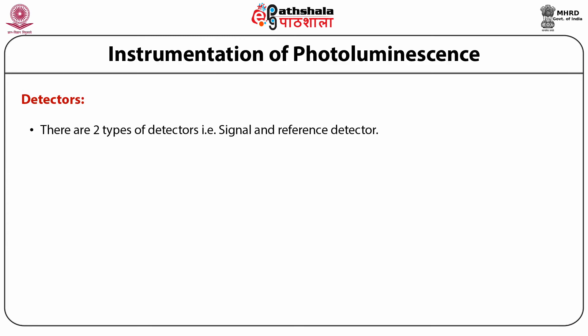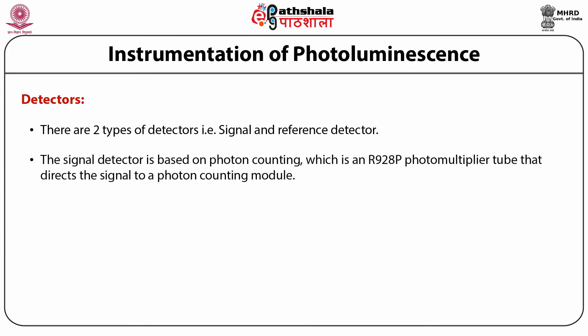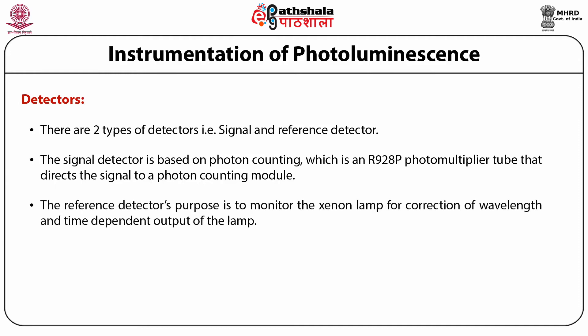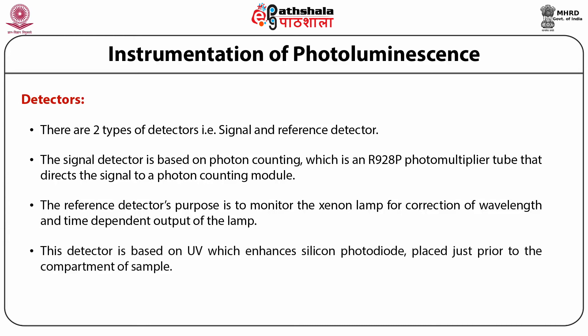There are two types of detectors: signal and reference detectors. The signal detector is based on photon counting using an R928P photomultiplier tube that directs the signal to a photon counting module. The reference detector monitors the xenon lamp for correction of wavelength and time-dependent output of the lamp. This detector is based on a UV-enhanced silicon photodiode placed just prior to the sample compartment.